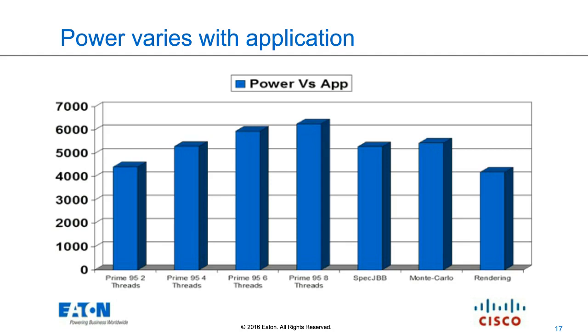It's really about the power difference between this benchmark called Prime95 running 2 threads versus running 8 threads, which goes from about 4250 watts to 6,000 watts across this system. SpecJBB, another benchmark, was pulling about 5,000 watts. This was a customer application, a Monte Carlo simulation used for options and trading, pulling just over 5,000 watts. And this rendering solution, doing film or image compositing for animations, was pulling about 4,000 watts.